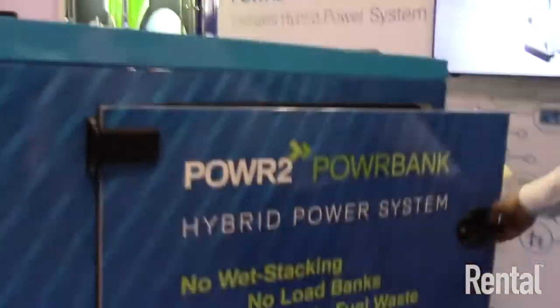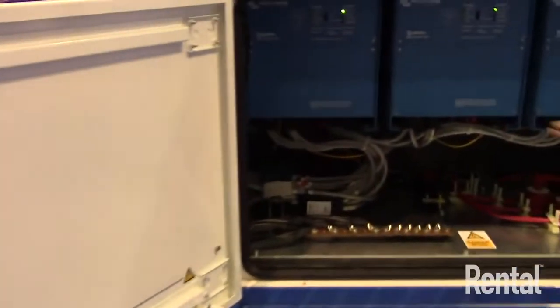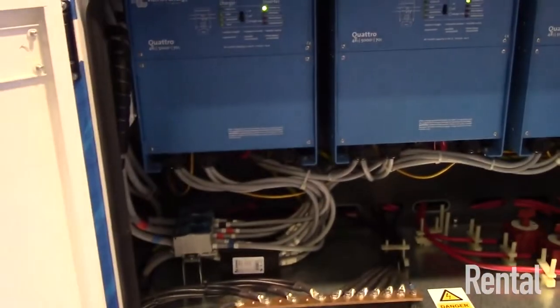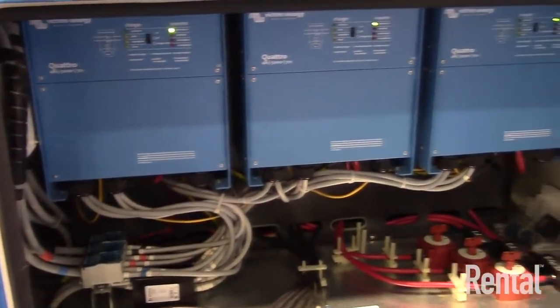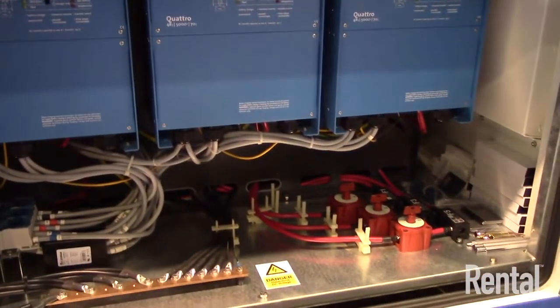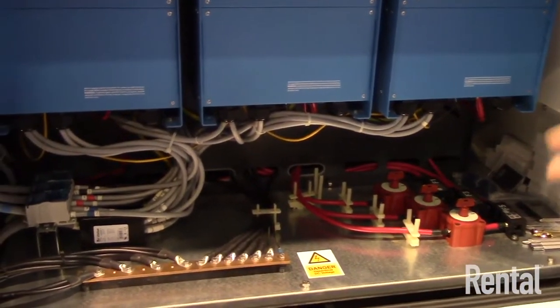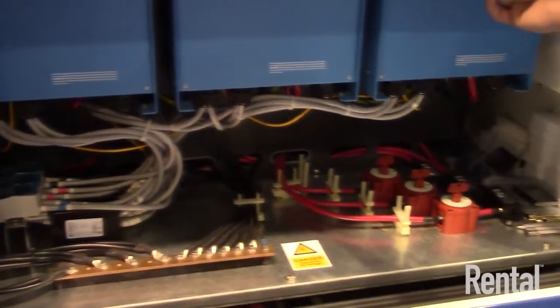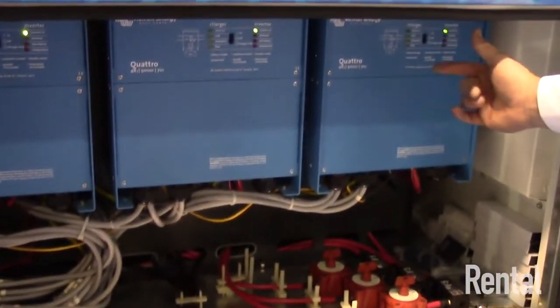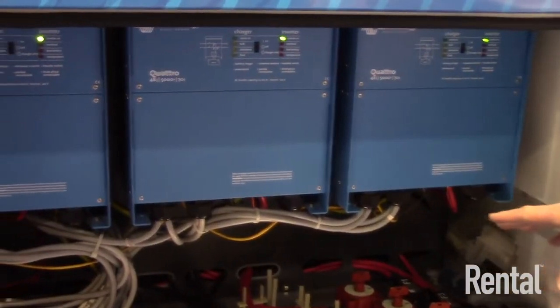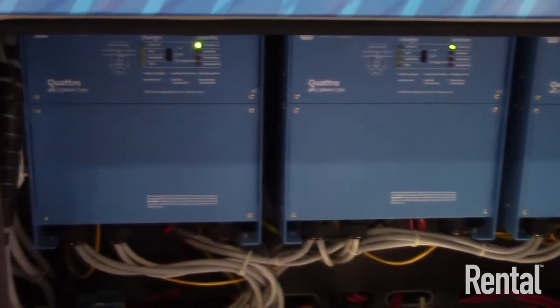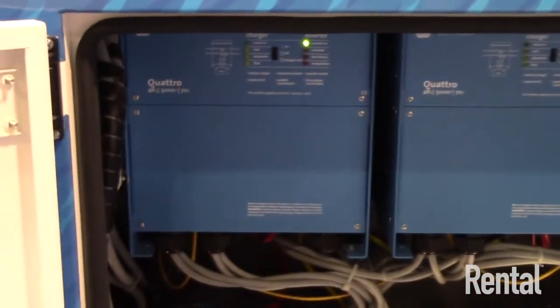The first component, as with any energy storage system, is obviously the battery. So the whole base of our system is high density lithium ion batteries, and then it comes up with 48 volt DC power from the batteries through our inverters, which is the second major component, that translates that voltage from 48 volt DC to 208 volt three phase on the output side.